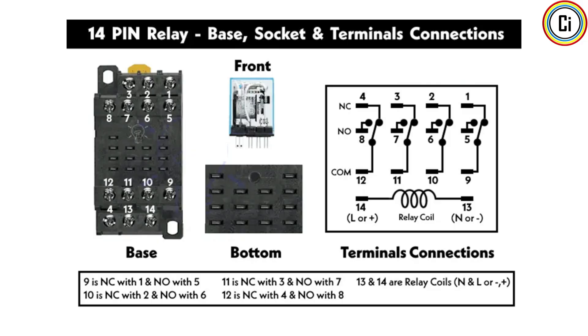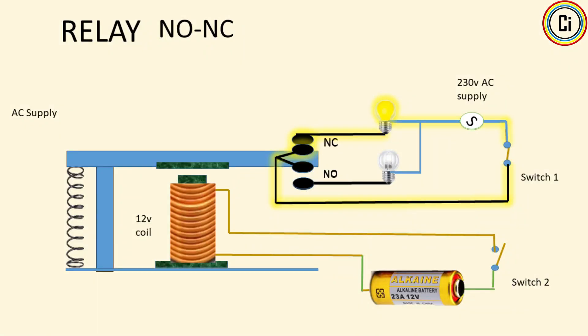The relay is built with a coil, iron core, moving armature, spring, and contacts inside a transparent housing. Out of the 14 pins, pin 13 and 14 are for the coil. The other 12 pins form four sets of common, normally closed (NC), and normally open (NO) contacts.